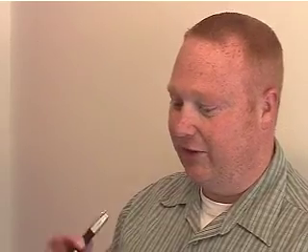Generally with the thermostats, the issue you might get as far as calibration might be a bad location of the sensor. You have other devices affecting them, a current, something maybe behind the wall blowing against it. They shouldn't go out of calibration is what I'm getting at. But we can calibrate if need be. So if you're getting a reading that doesn't seem feasible to you guys, we can put an offset in there to calibrate those sensors as well.